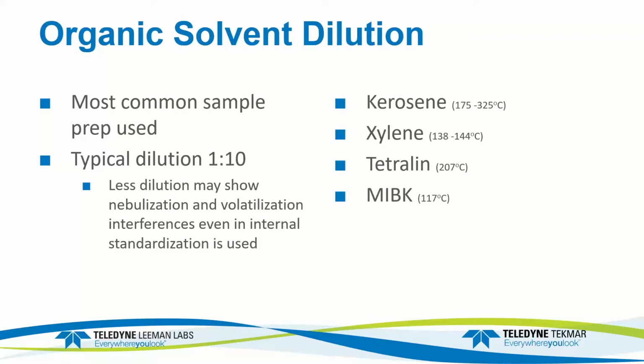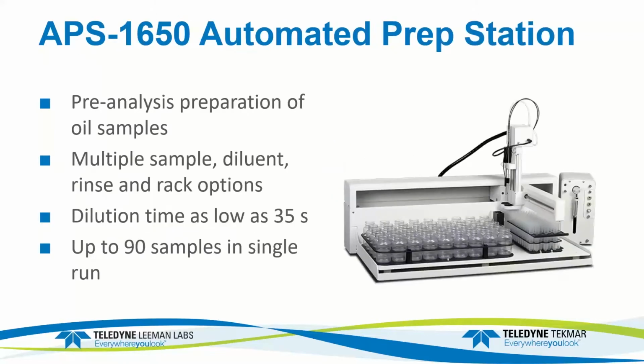By far, the most common solvent for the oils for wear metals is kerosene. Some of the others can be used depending on, some oils are actually better with xylene, but by far most people use kerosene. So in this case, we use kerosene. It is possible to also automate the sample preparation stage with the APS 1650 that allows people to put on a bunch of oil samples, and then they get diluted and put into the smaller test tubes, and then that rack goes right from the APS 1650 right into the OES 7400, so minimizing the amount of sample handling that the individual operator has to do.